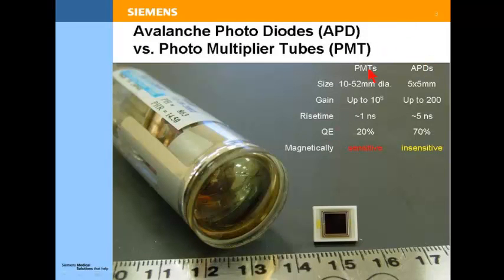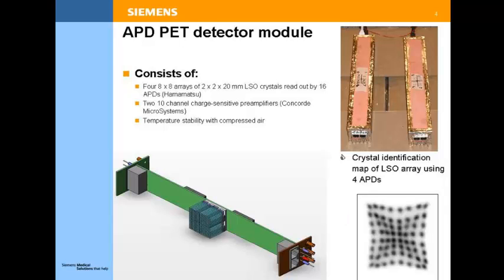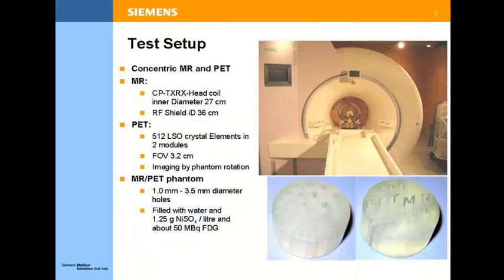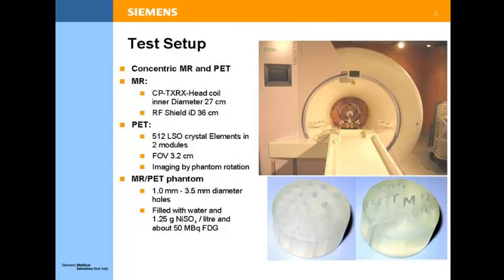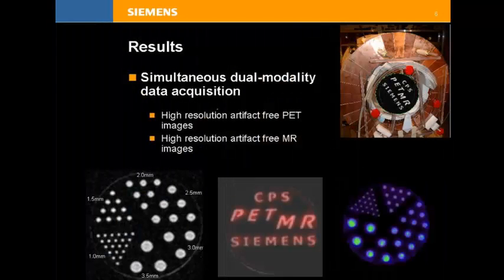Comparing photomultipliers and APDs: APDs are much smaller, have smaller gain, a slightly slower rise time, and are not sensitive to MR. However, with APD technology you cannot perform time-of-flight PET imaging. The detector arrays consist of four 8x8 arrays of LSO crystals with avalanche photodetectors that are very stable to temperature. This was the first prototype developed as a head insert with the fibers outside for computing, and the resulting images showed very good PET quality with resolution down to one millimeter in phantom settings, as well as very good MR quality.